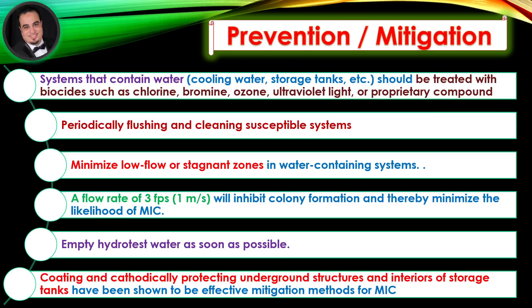Systems can be treated with biocides such as chlorine, bromine, ozone, ultraviolet light, or proprietary compounds. Periodically flushing and cleaning susceptible systems is recommended. Minimize low flow or stagnant zones in water-containing systems. A flow rate of three feet per second will inhibit colony formation and thereby minimize the likelihood of microbiologically influenced corrosion.